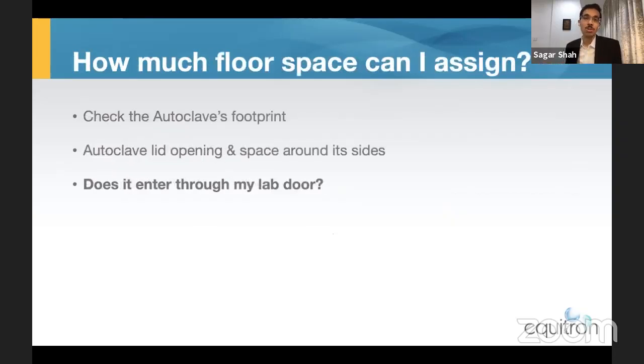You also need to check on the floor space that you can assign. You need to bear in mind that you will need to keep some space towards the sides of the autoclave for maintenance and service clearance purposes. And very importantly, whilst an autoclave may fit in the available floor space, people often miss out that it should be able to pass through your lab door as well. So that's something critical to evaluate when you're doing the evaluation of the autoclave.